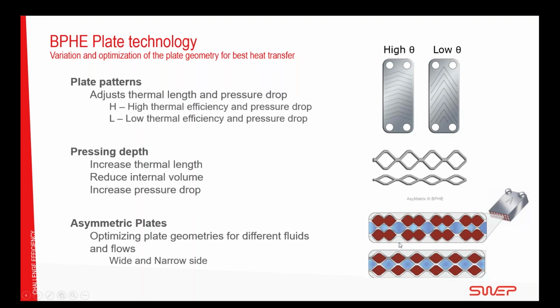And an asymmetric heat exchanger would be perfect in applications where gas and liquid meet, like a superheater. A superheater would be perfect with an asymmetric plate where gas goes in the wide side and water goes in the narrow side, or an oil cooler where you have the viscous oil going on the wide side and the lighter water going on the narrow side. If you have water to water, you will probably benefit from using a symmetric heat exchanger.